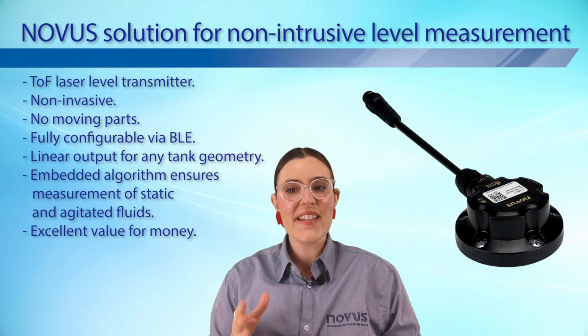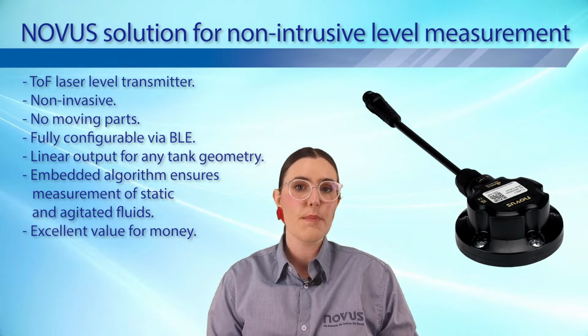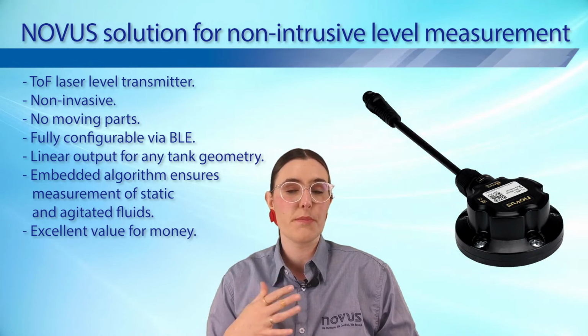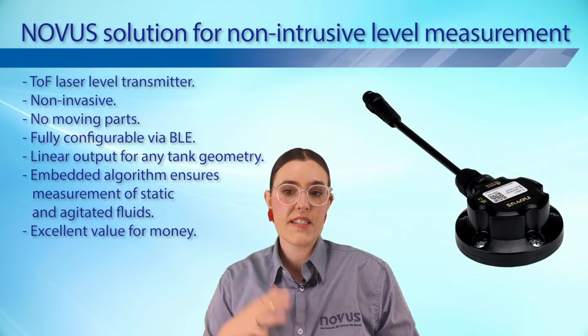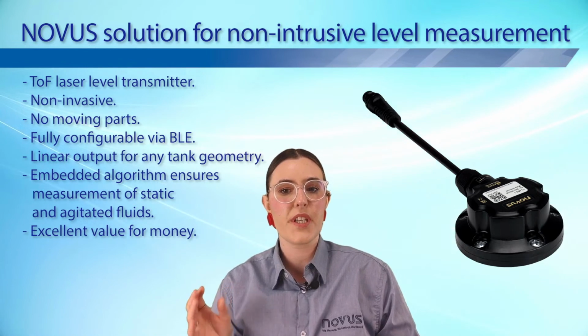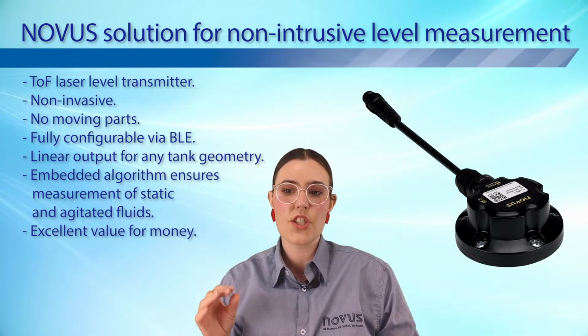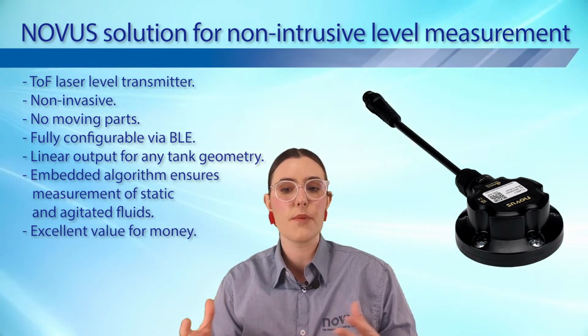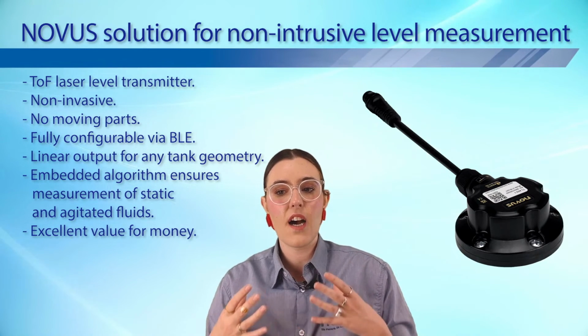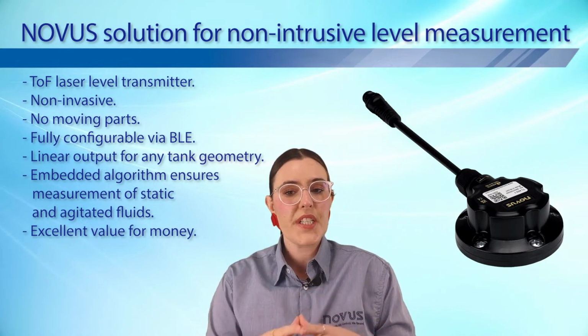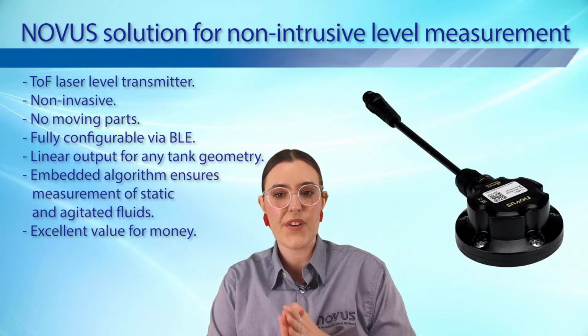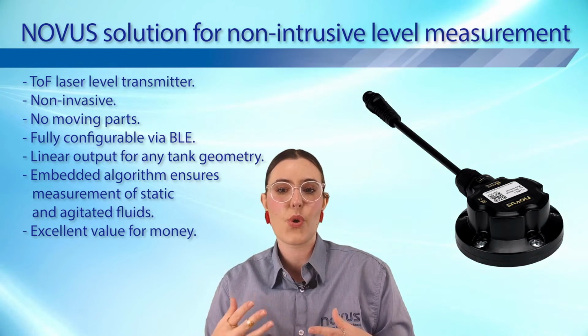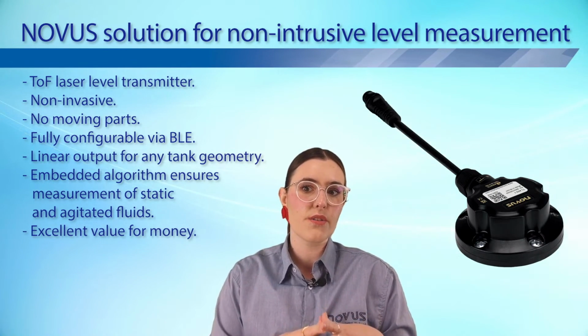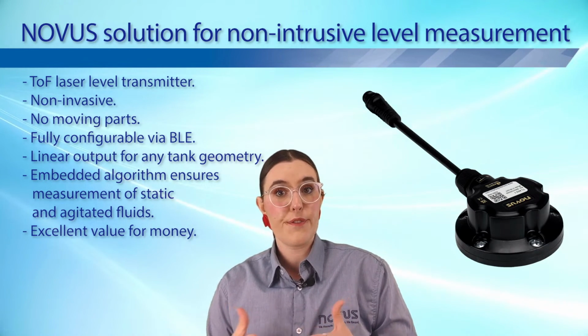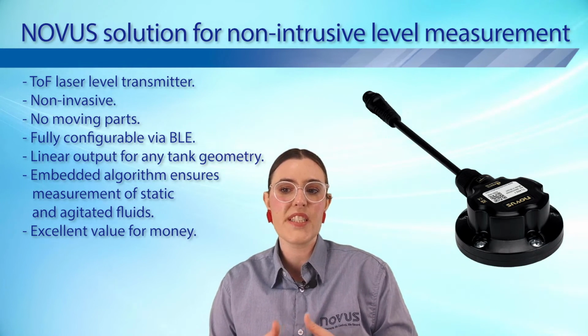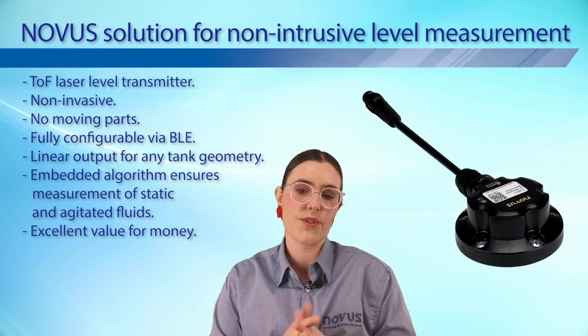So TL400-I, the latest development in the NOVUS sensor area, uses the time of flight principle through a class 1 laser beam, which is completely harmless to human vision. Its output not only retransmits level, but can also be configured to measure distance and volume. It is non-intrusive, so the sensor does not project itself into the tank and does not come in contact with the product being measured. During the development of this product, numerous tests were carried out with different materials and usage conditions, allowing us to acquire the know-how to embed a statistical algorithm into this device. Therefore, TL400-I can perform readings even in agitated liquids, such as in vehicles, for example.